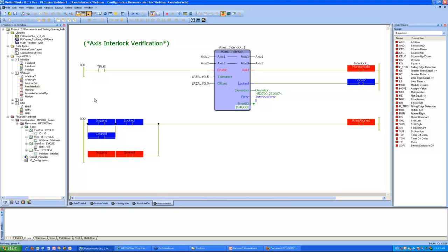So we have plans to add another function block called Y reboot controller, which would be a more appropriate name for a function describing the behavior that one would have on the MP2600. And that would basically allow you to accomplish a very similar sequence as we just showed here to clear the amplifier alarms that need a power cycle, with the additional caveat that the controller itself is also resetting. So there would be some slight difference in performance or in behavior there.